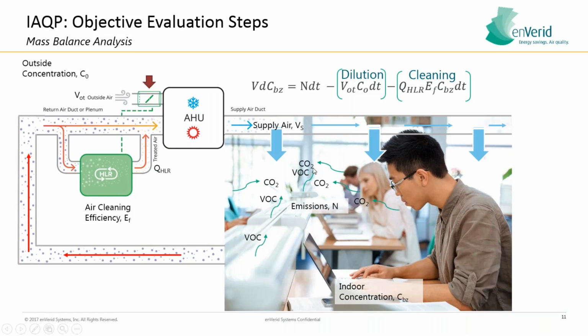Now, how are you sizing these systems? enVerid, because we remove CO2, which is a very unique component about the enVerid solution, we remove CO2 and all other VOCs as well. Basically, we calculate our systems according to occupancy. We know we can remove formaldehyde and all the other contaminants faster than they're emitted within spaces based on the mass balance equation. CO2 is our limiting contaminant of concern.